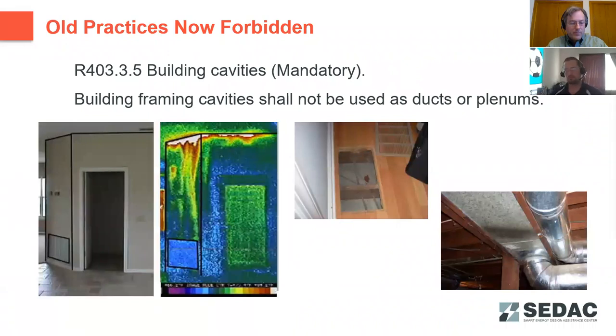Why has duct pressure testing become so important? Over the years, we've done testing and analysis and discovered that unsealed ductwork can have detrimental impacts. Here you can see a thermal image of a return duct in a wall that's drawing attic air into that return system. Not only is that increasing the load that unit must now condition, it's also drawing in impurities and dust and things from that attic space.